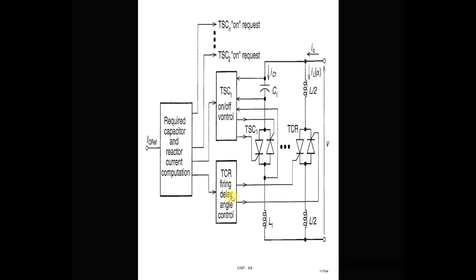Now this is all about how to provide transient free operation when you control the switching of the thyristor switched capacitor branch. As we know, the capacitor cannot be switched at any firing angle delay because of transient free operation. If you switch on at any firing angle delay, it creates a high switching transient, called a capacitor switching transient, which can damage the thyristor and also affect the transient stability of the power system. So because of that, the thyristor cannot be fired at any firing angle delay.